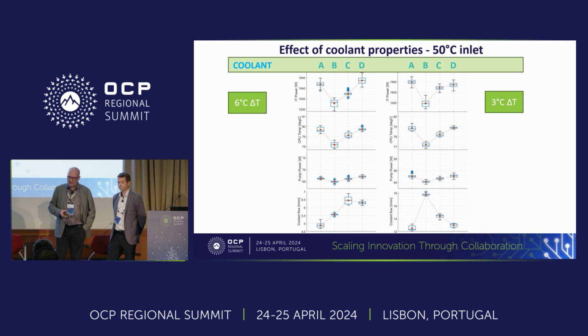And why is the CPU temperature lower? I mean, that's something we can talk about a little bit in a minute. But also the pump energy, the third line there, shows a decrease. This is all happening at 50 degrees centigrade inlet. So you can see that the temperatures of the CPUs are getting close to their non-ideal case. 80 degrees is quite hot for these. But there's one there that's at 78.